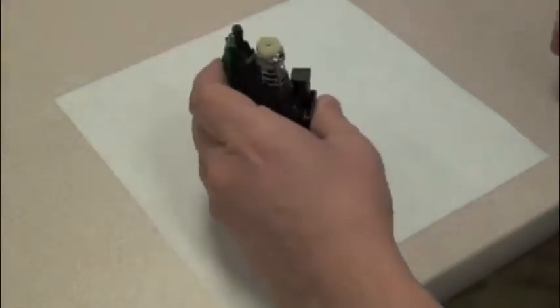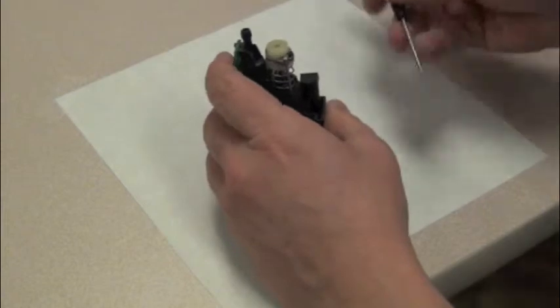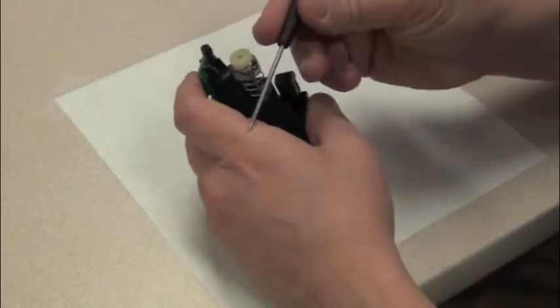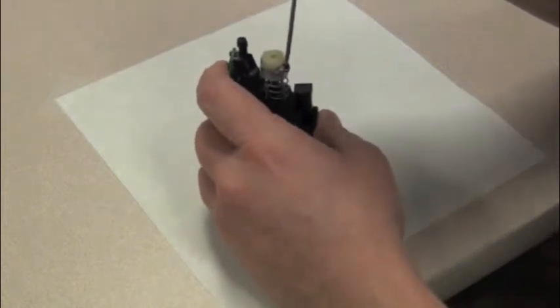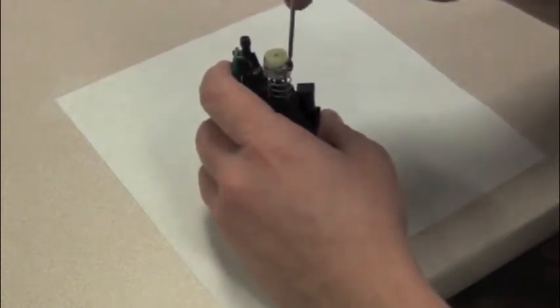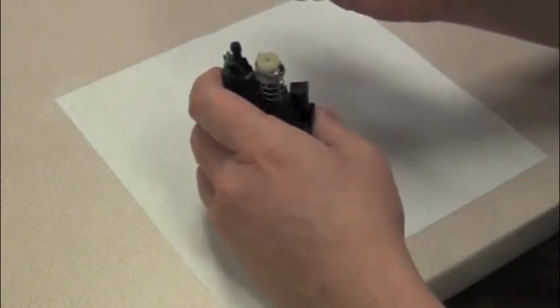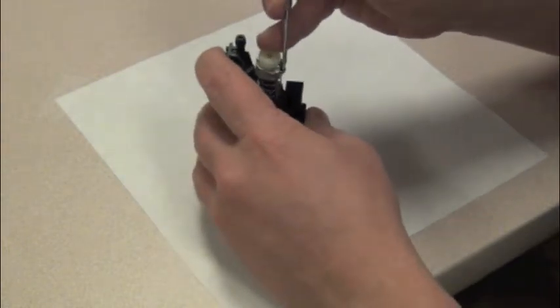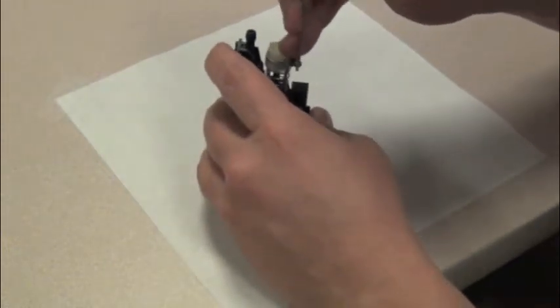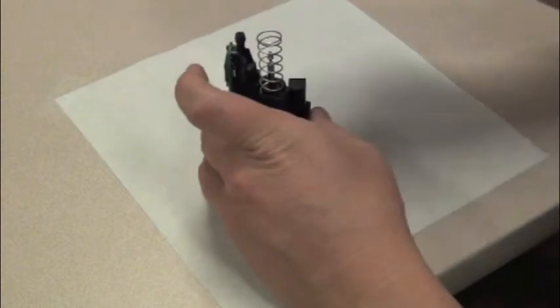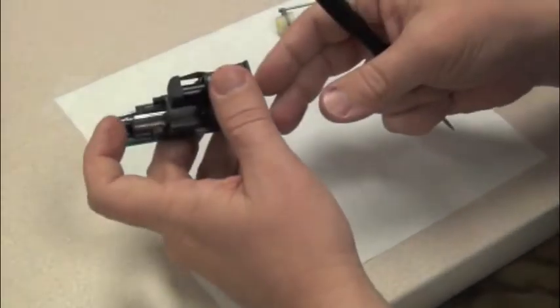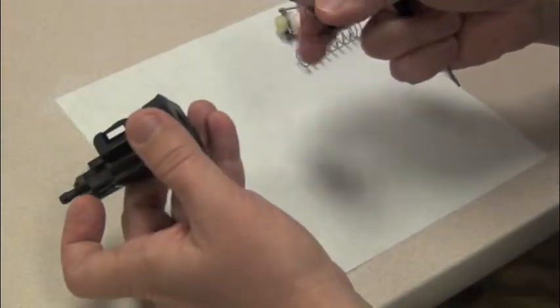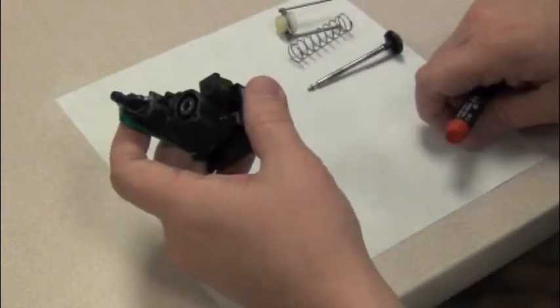Let's start by removing the spindle guide cap. I'm going to take a 1.5 millimeter wrench and loosen this top screw two or three turns. Then I'm going to take the same wrench and place it in the hole right beside the screw, slide it forward, take the spindle guide cap, place it to the side, take the spring out, place it to the side, take the spindle, push it out through the bottom, and place that to the side.